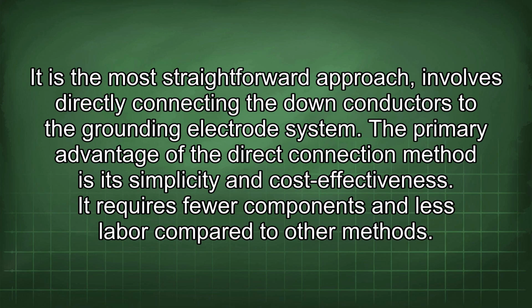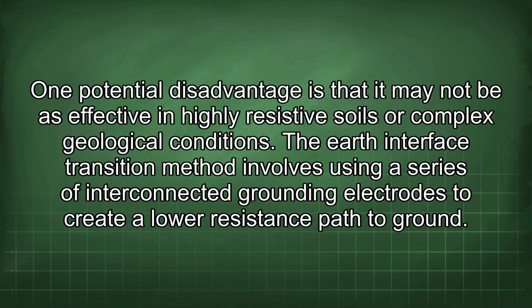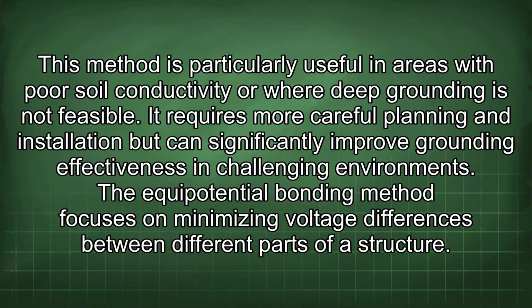The primary advantage of the direct connection method is its simplicity and cost-effectiveness. It requires fewer components and less labor compared to other methods. One potential disadvantage is that it may not be as effective in highly resistive soils or complex geological conditions. The earth interface transition method involves using a series of interconnected grounding electrodes to create a lower resistance path to ground. This method is particularly useful in areas with poor soil conductivity or where deep grounding is not feasible. It requires more careful planning and installation, but can significantly improve grounding effectiveness in challenging environments.